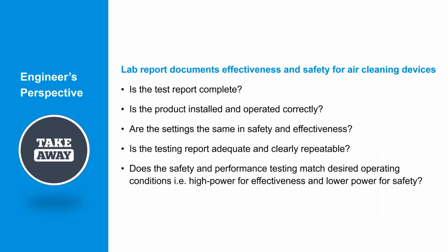And so that's really part of this perspective. I jumped ahead on this, but hopefully what you'll see is that both the effectiveness and the safety tests give you good confidence by understanding how to read the test report. I would suggest that you add this into your specifications if you are going to include electronic air cleaners. It's really a watershed moment for the category, and I think it's a big step forward that ASHRAE has done as a favor to the entire industry, to help provide boundaries for what is an appropriate solution to provide better air quality within these spaces that we're designing.